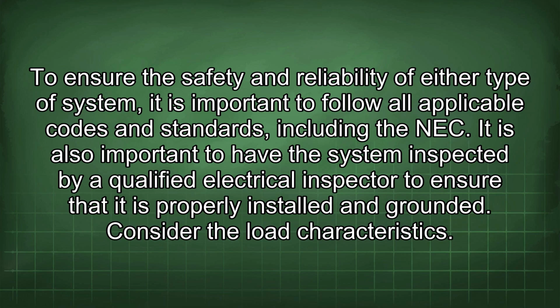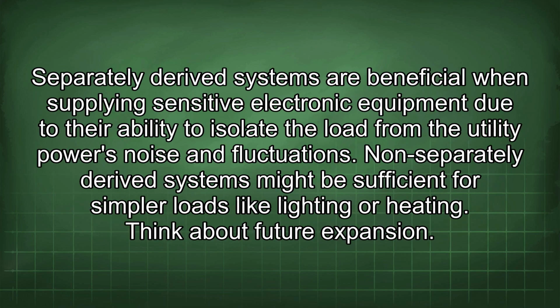Consider the load characteristics. Separately derived systems are beneficial when supplying sensitive electronic equipment due to their ability to isolate the load from the utility power's noise and fluctuations. Non-separately derived systems might be sufficient for simpler loads like lighting or heating.